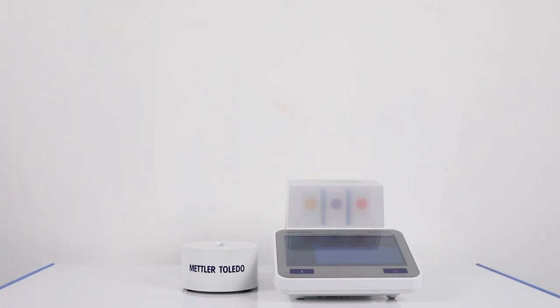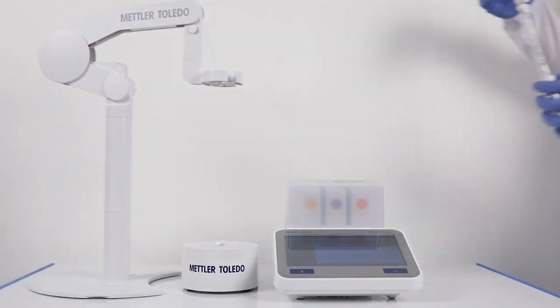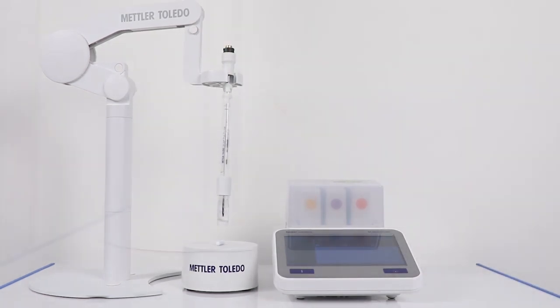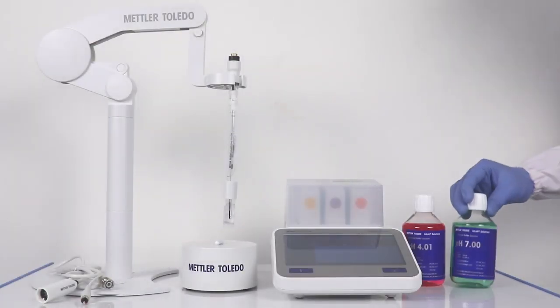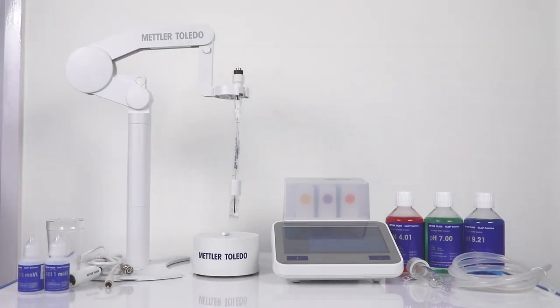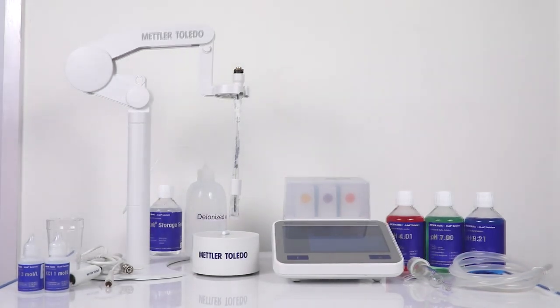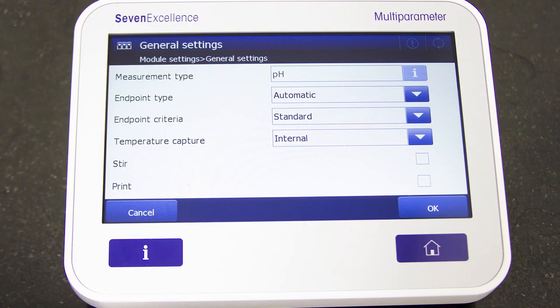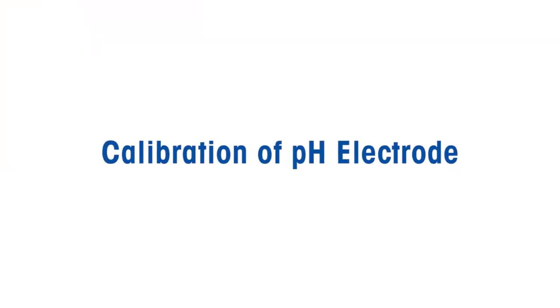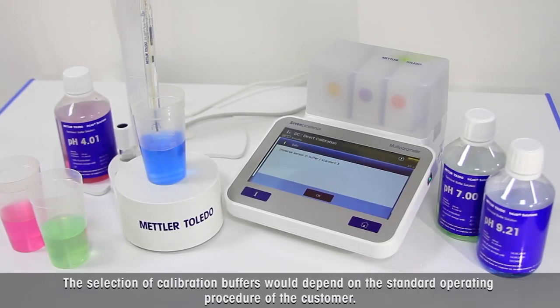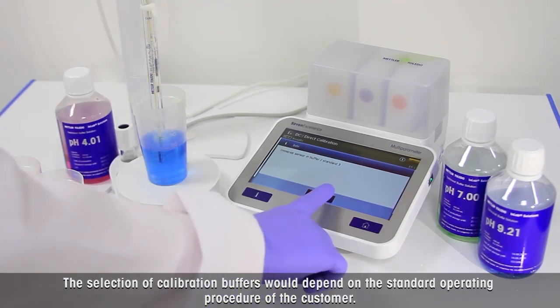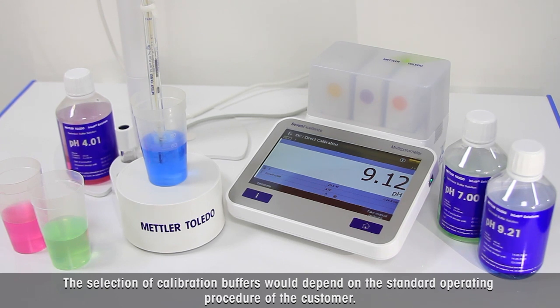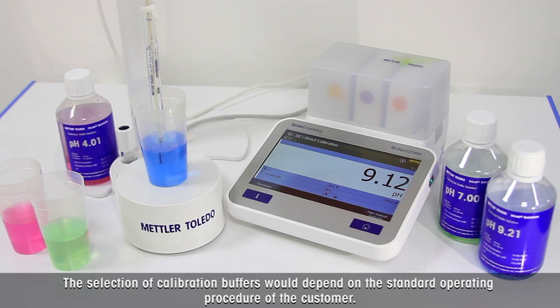For the pH measurement in pure water, we need a pH meter with a U-Mix magnetic stirrer, U-Place electrode holder, InLab Pure Pro ISM sensor, and multi-pin cable, buffer solutions, glass beakers for samples, a flow cell, maintenance solutions. The calibration and the measurements are carried out with automatic endpoint type and standard endpoint criterion. Use an electrode calibrated using standard buffer solutions pH 4.01, pH 7.00, and pH 9.21, such as to bracket the expected measurement value.